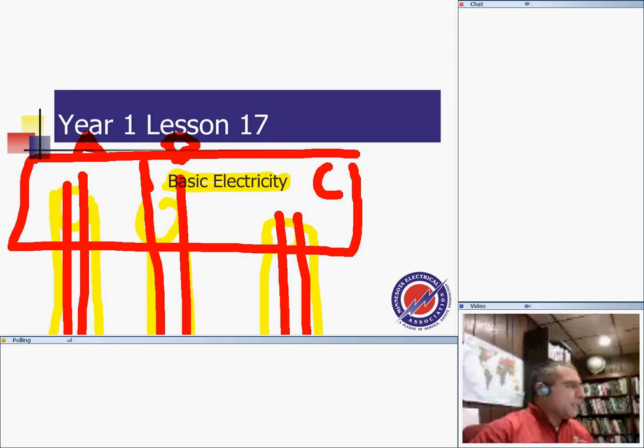Another thing says direct burial cables or conductors must generally be buried twice of. If you don't know what the condition is and you have a cable that is direct buried, you bury it at 24 inches. That's kind of the worst of the worst. This one says all temporary 120 volt receptacles need to be part of ground fault circuit interrupter protection for personnel. Temporary wiring, like construction and so forth. Any 120 volt, 15, 20, and 30 amp non-locking receptacles have to be GFCI.